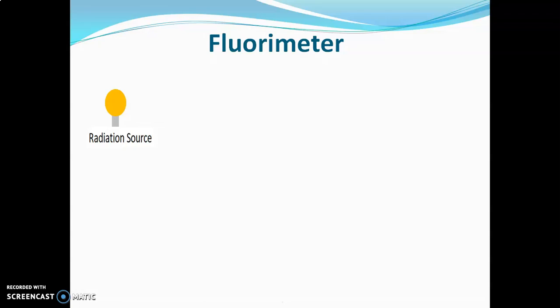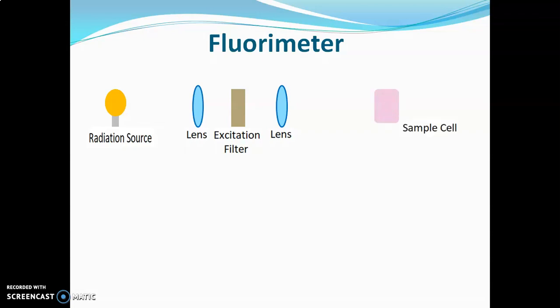A fluorimeter consists of a radiation source which emits radiations. Next is a collimating convex lens which collects the radiations emitted by the source and focuses it towards the excitation filter. The excitation filter absorbs visible radiations and only UV radiations are allowed to pass. Next is a focusing lens which focuses the UV radiations towards the sample cell, which holds the sample.